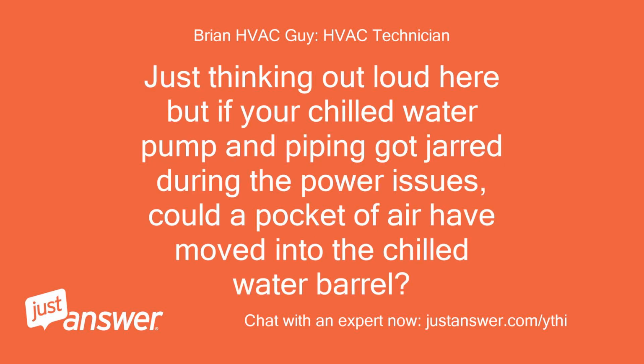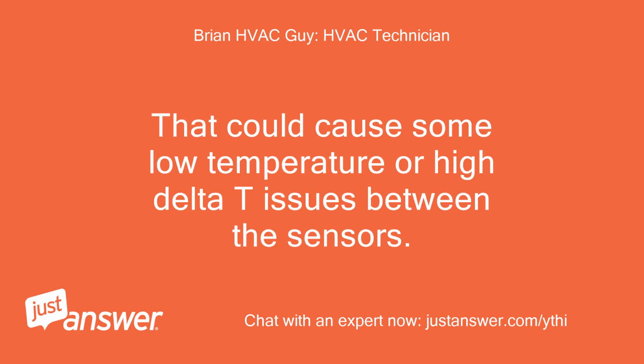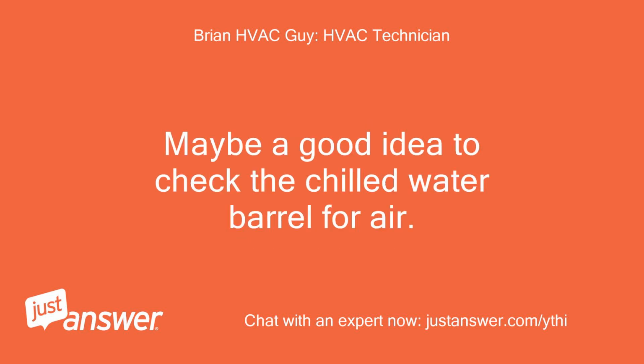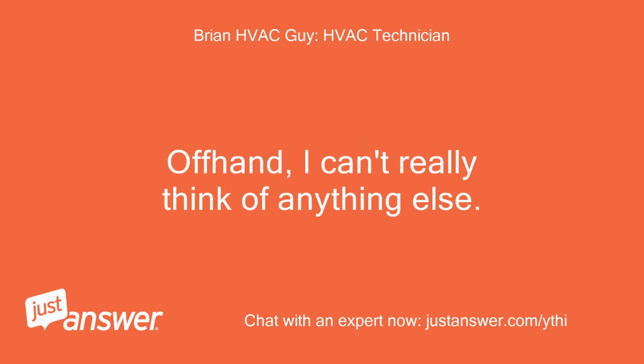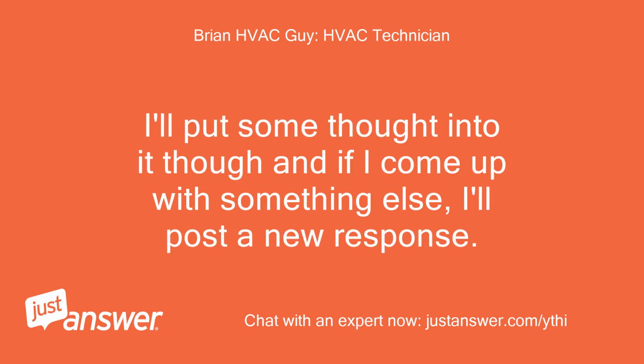Just thinking out loud here, but if your chilled water pump and piping got jarred during the power issues, could a pocket of air have moved into the chilled water barrel? That could cause some low temperature or high delta T issues between the sensors. Maybe a good idea to check the chilled water barrel for air. Offhand, I can't really think of anything else. I'll put some thought into it though, and if I come up with something else, I'll post a new response.